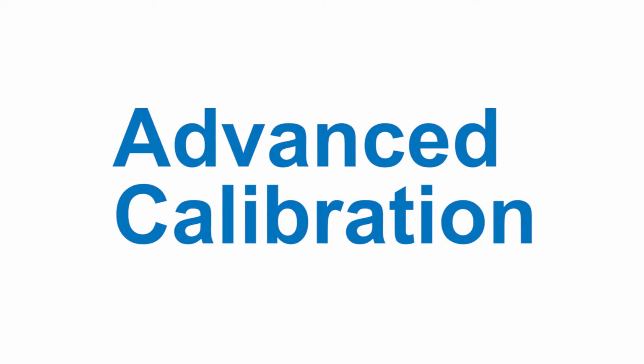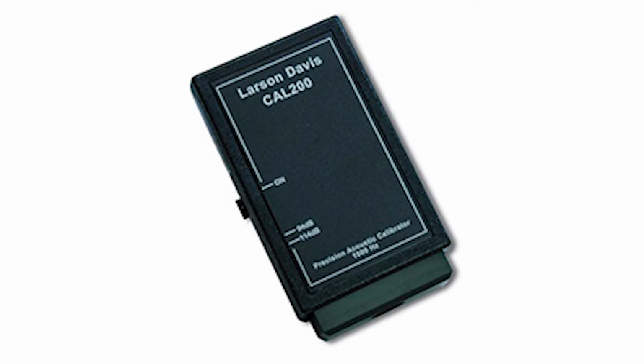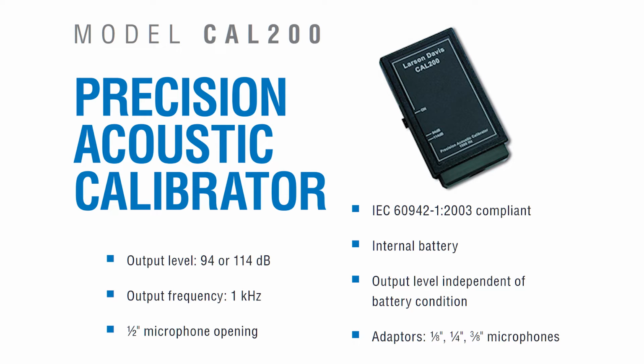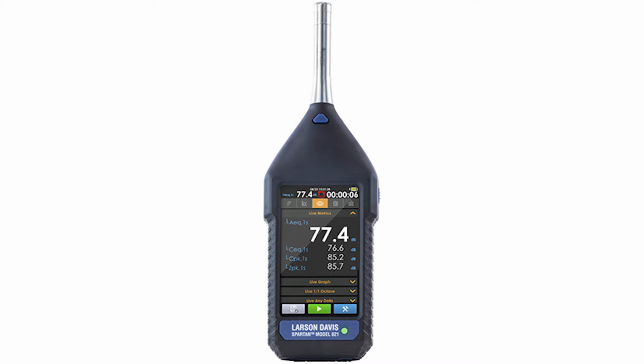Advanced calibration. In acoustic calibration, the sound level calibrator, in this case either the CAL150 or the CAL200, provides an acoustic signal of a known amplitude, 94 or 114 decibels, and frequency, 1000 Hz, to the microphone, which is used as a reference to adjust the system sensitivity. In the meter, the system sensitivity updates with each calibration. We recommend that you calibrate prior to each measurement.